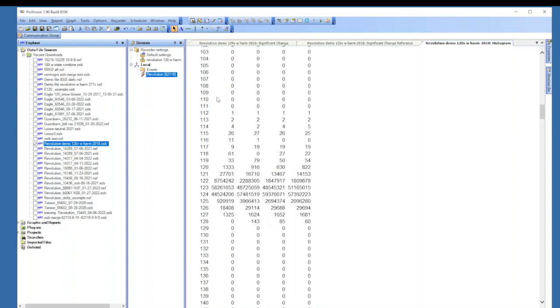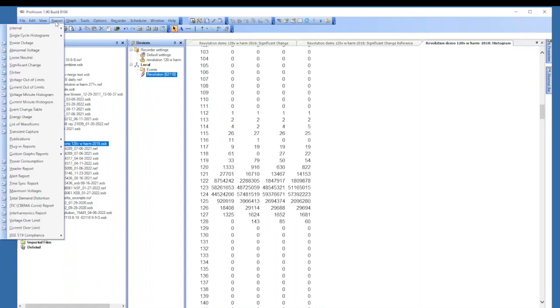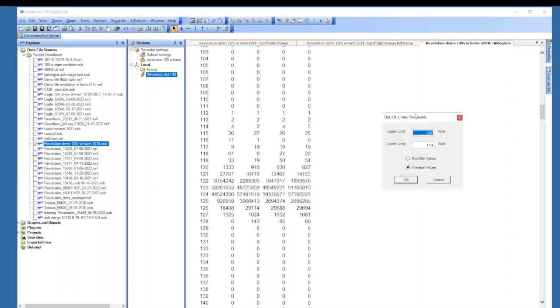127.6. And the one thing is, once you see this, you can go to your report again, and there's a voltage out of limits. And sometimes you get a lot of zeros, voltages. So if you don't want to get too many, and you do have a lot of numbers down in the zeros, just put a 0 there. And then we're going to put 127 here and mins and maxes. And we can see when some of those voltages occurred. So channel 2 had 127.6. So these all occurred on 515 and then another one on 529. And neither of those are our start or stop time.